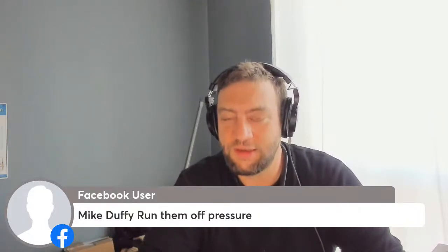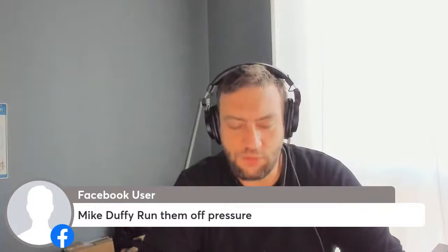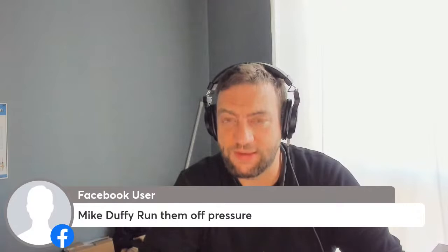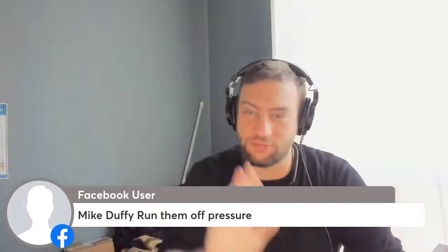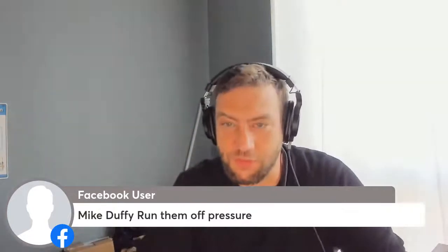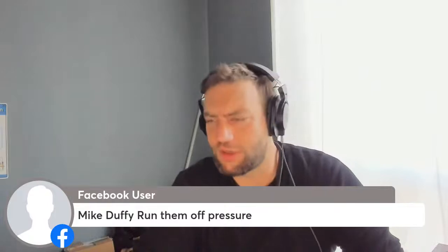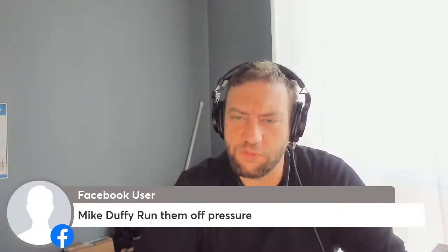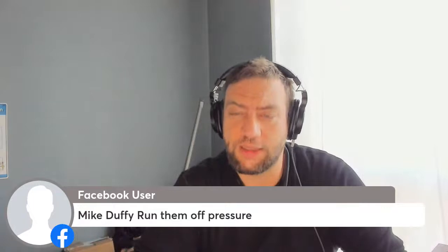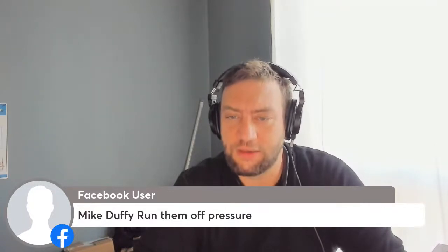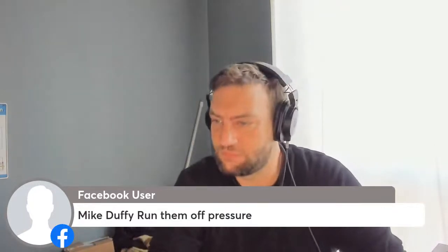We've done that in the past on racks that were trying to maintain a subcooler temperature, but then the valve would just go all over the place, up and down. So we decided to do a loop sequencer where that valve was trying to achieve that pressure. It's actually a good one. We could do something like that, where we do a loop sequencer and show you how to link it up to a CDS valve in order to do that. That's a good one.